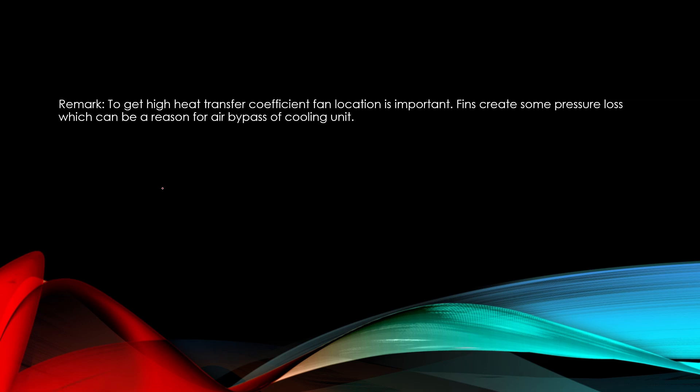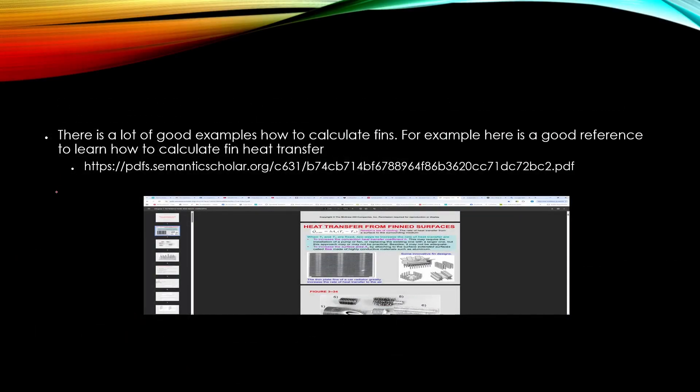These were the results and what I want to point out is that when you design this kind of cooling elements, it's not only the design of those fins, but you need to take care of that convective heat transfer. Because those fins are creating some pressure loss for airflow. It easily creates a situation that your cooling air will bypass the cooling unit. Be very careful when you locate your fan.